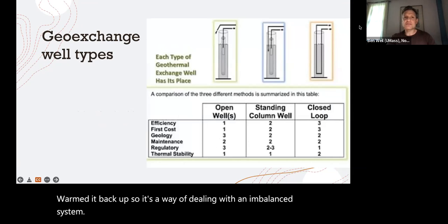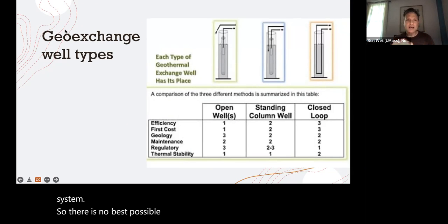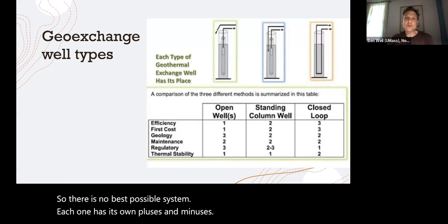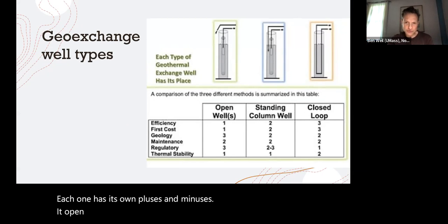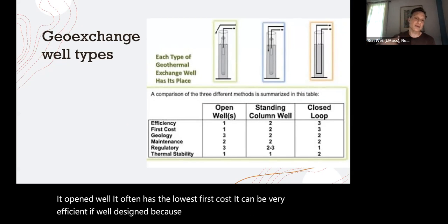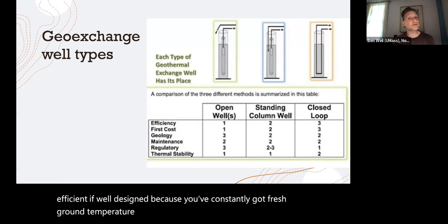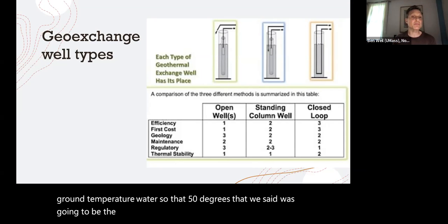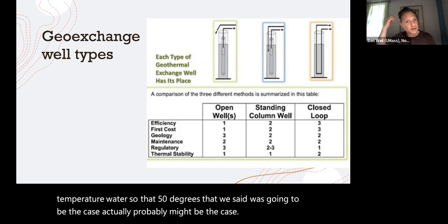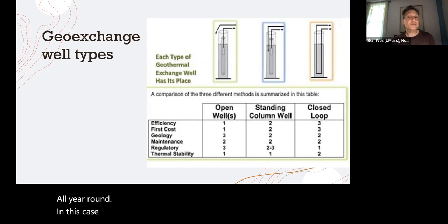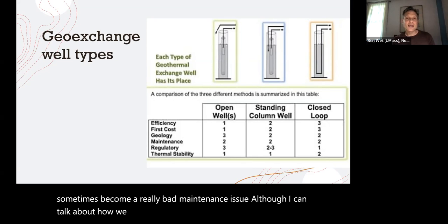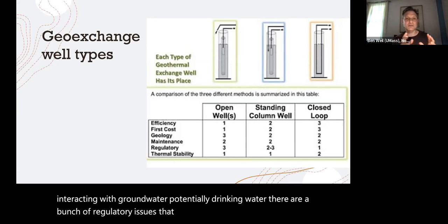So there is no best possible system. Each one has its own pluses and minuses. An open well often has the lowest first cost. It can be very efficient if well designed, because you've constantly got fresh ground temperature water. So that 50 degrees that we said was going to be the case actually probably might be the case all year round in this case. But the geology has to be just right. And you have a maintenance issue that I mentioned with filters. And that can sometimes become a really bad maintenance issue, although I can talk about how we can reduce those. And because you're interacting with groundwater, potentially drinking water, there are a bunch of regulatory issues that have to be dealt with, but it's very thermally stable.